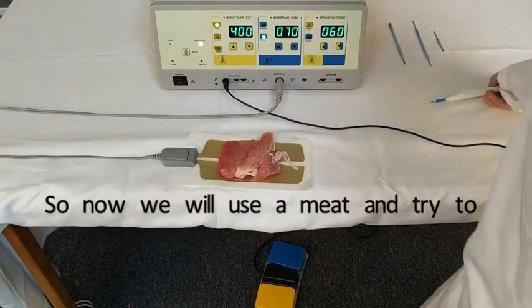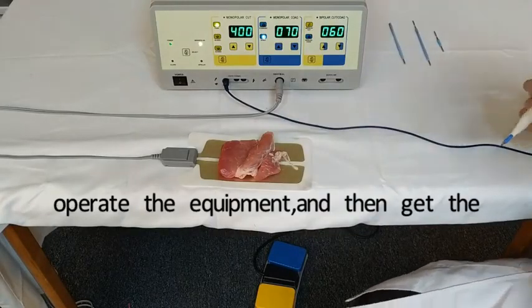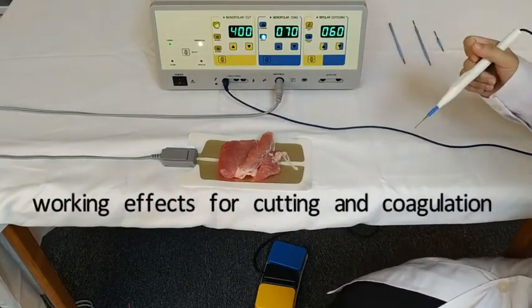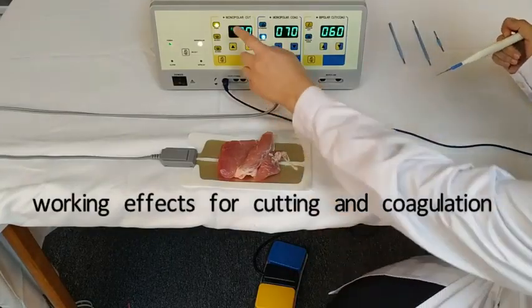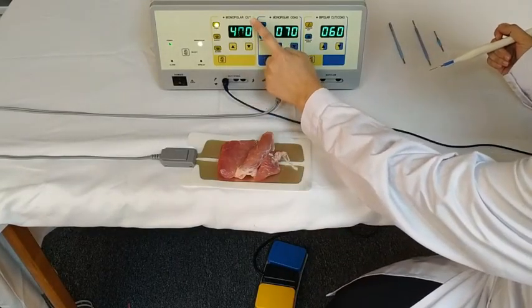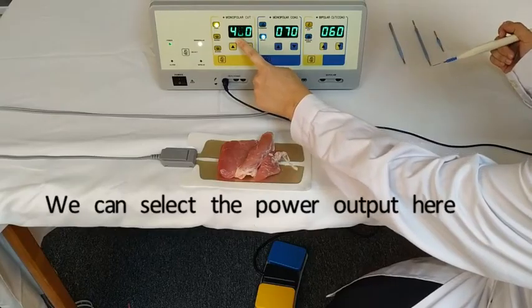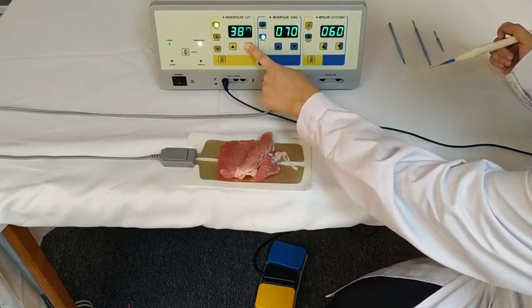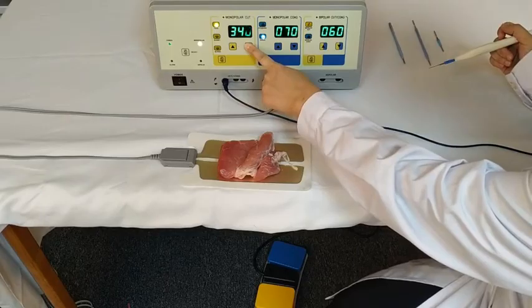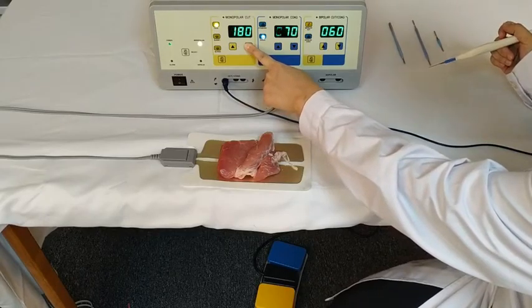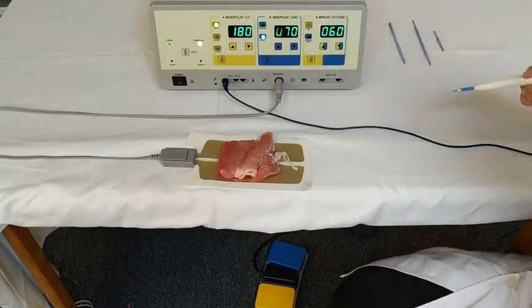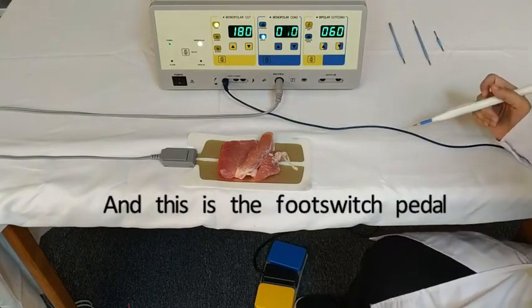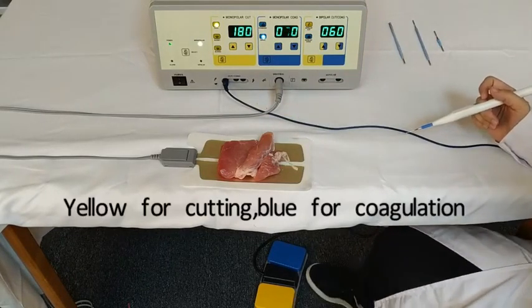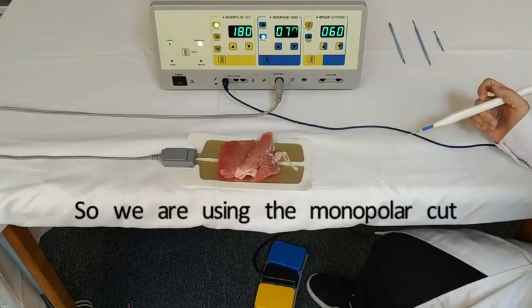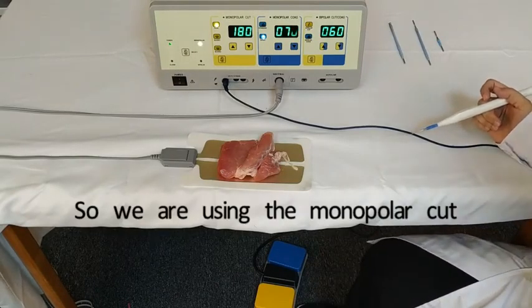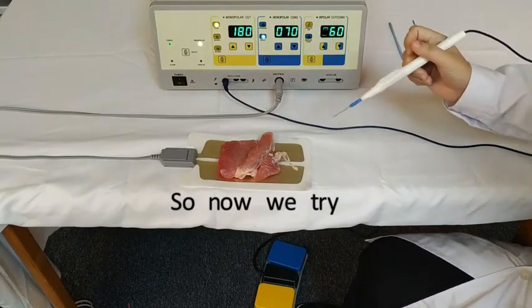So now we will use a meat and try to operate the equipment and get the working effect for cutting and coagulation. Here is pure cut. We can select the power output here. And this is the foot switch pedal. Yellow for cutting, blue for coagulation. So we are using the monopolar cut. So now we check.